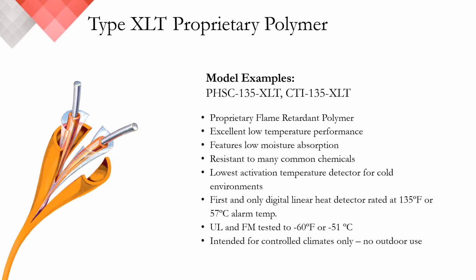Every digital linear heat detector has a maximum ambient temperature in which it can be applied. Our XLT series is no exception. With the lowest initiation temperature of any digital linear heat detector at 135 degrees Fahrenheit or 57 C, it also has a maximum ambient temperature of 100 Fahrenheit or 38 C and is only recommended for climate-controlled environments.